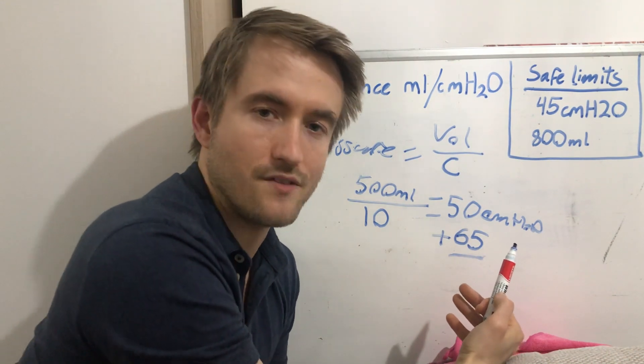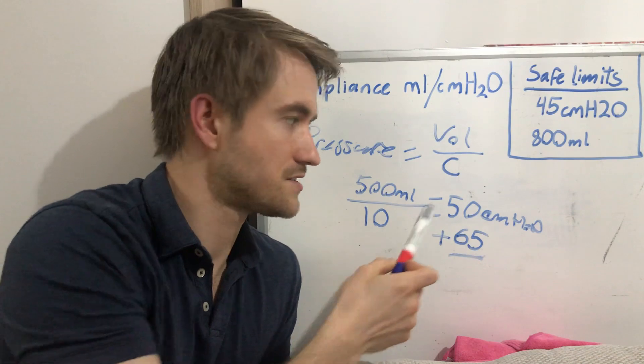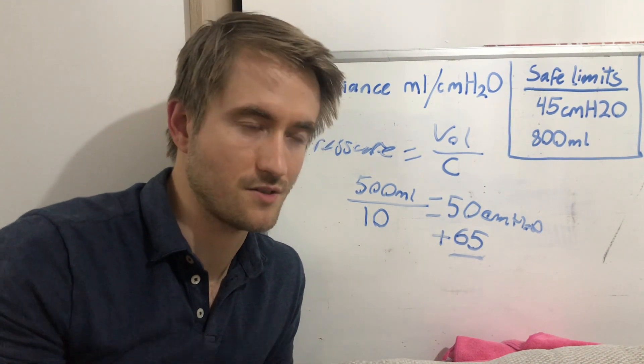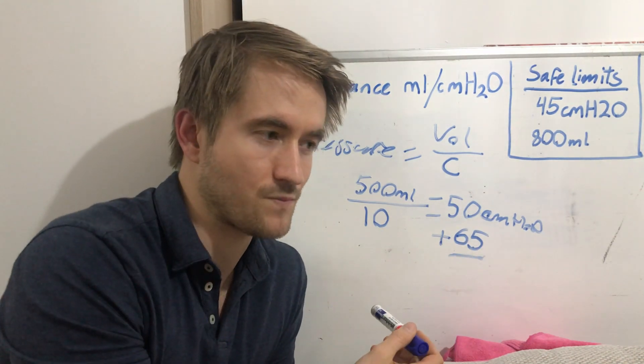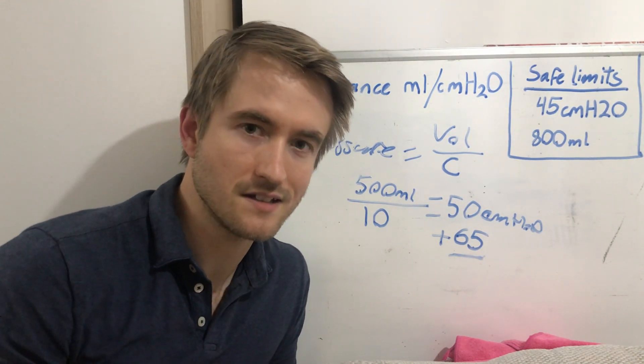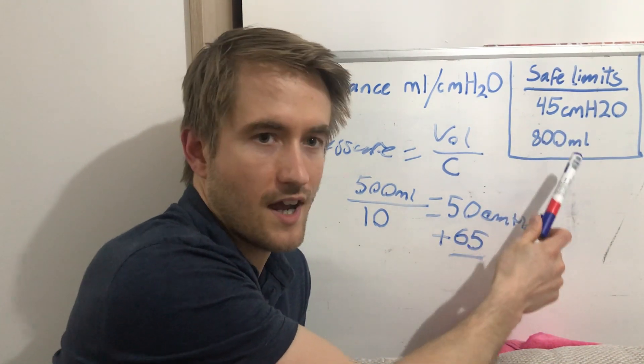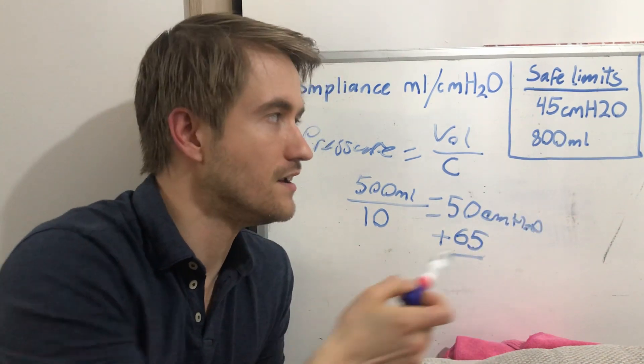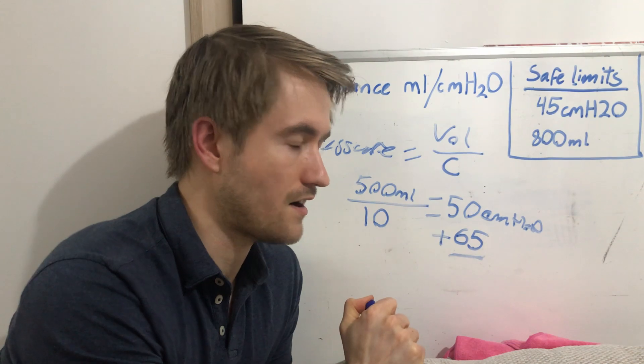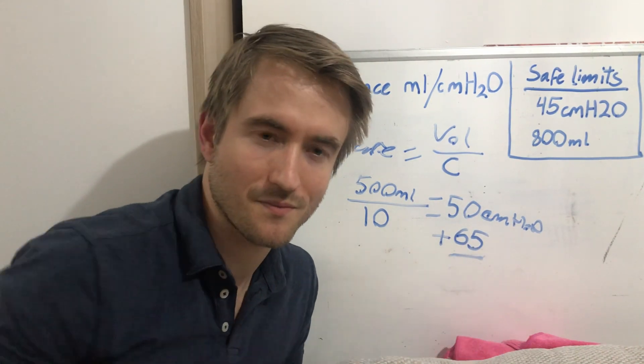So the question is: where does that leave us? We're trying to design a system to meet the MHRA requirements, but part of the requirements suggests 35 cmH2O as a number we shouldn't exceed, while the test table requires pressures much higher than that to satisfy certain tests. I'm thinking that test table may not reflect their original intent. I don't want to design a system producing unsafe pressure or volume levels, so for now we'll stick to 45 cmH2O as the maximum our device can achieve. The test table probably needs another look. Any questions, please put them in the comments. Thanks.